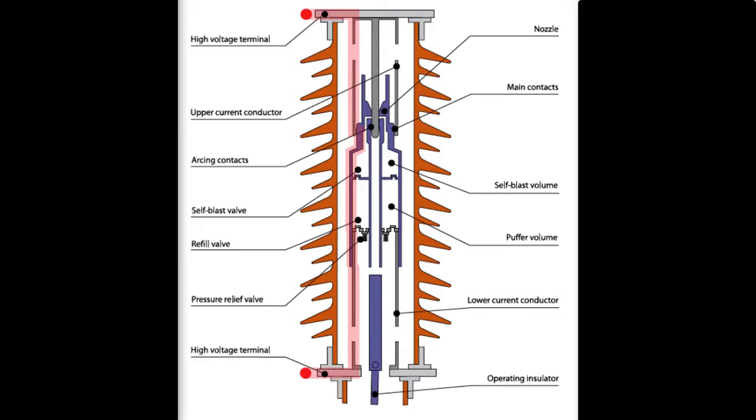If the current is low enough to not cause the breaker to self-blast, the topology of the breaker operates normally. As you may suspect, a self-blast breaker requires more maintenance after a self-blast event than a standard puffer breaker does before it is in normal operation condition again.